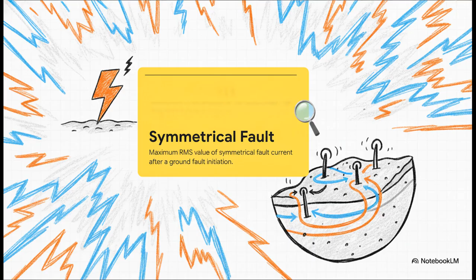Well, when a fault happens, it generates what engineers call the symmetrical ground fault current. Put simply, this is an incredibly intense, immediate release of electrical energy in the very first fraction of a second after a fault initiates. To handle this, substations absolutely must have a robust, completely invisible system to catch this violent surge of current and dissipate it harmlessly into the earth. And that brings us to the hidden reality beneath every major substation. It's a literal life-saving infrastructure.